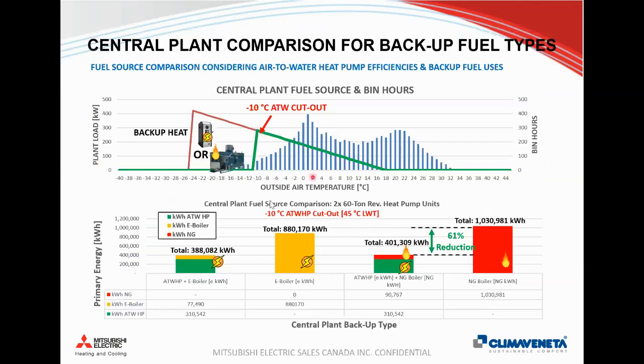If we just look at that -10 example, here we're going to compare using an electric heat pump within this green triangle down to -10, covering off these bin hours. And for the low frequency of hours that we have here, we're going to compare that to using a backup electric or backup gas, or all electric and all gas for the big triangle.